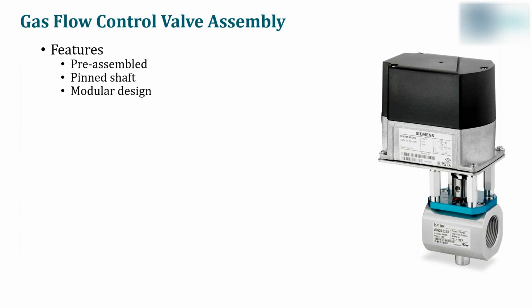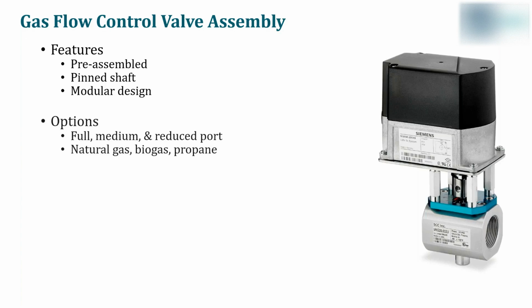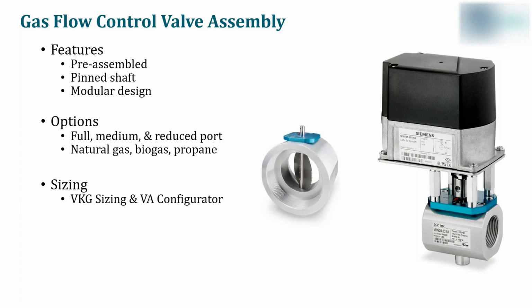Secondly, a pinned shaft. It guarantees no slippage. Once again, a safety issue SCC has addressed. And finally, a modular design. The options include either a full, medium, or reduced port valve. And also we make these for natural gas, biogas, and propane. In terms of sizing, we do have a VKG sizing program, and we will go and do an example of this right now.